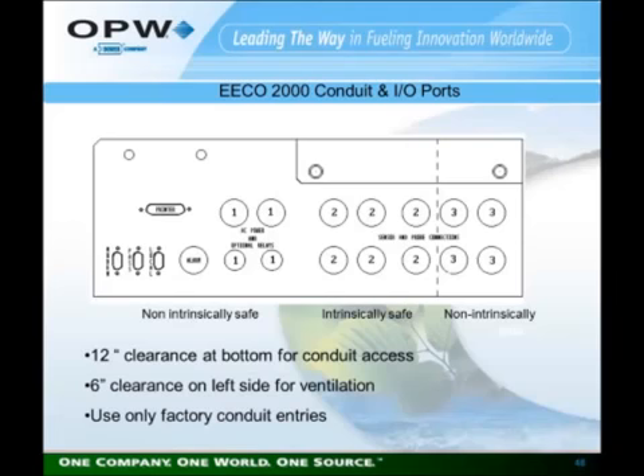The EECO 2000 conduit and input-output ports. The EECO 2000 has more ports on the bottom. You see that it's actually in 3 areas. We have non-intrinsically safe on the left, which is where the AC power connections and relay wire connections would be. We have intrinsically safe in the middle. That's where the probe connections and sensor connections would be. And then on the right are non-intrinsically safe. That's where the old line leak detector or dispenser power interface connections would be made.